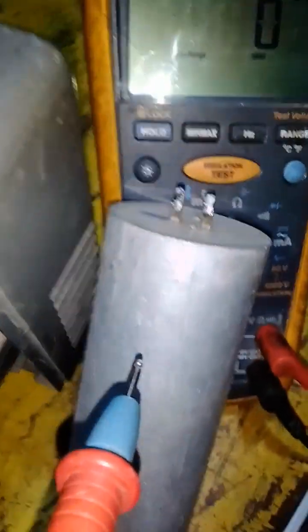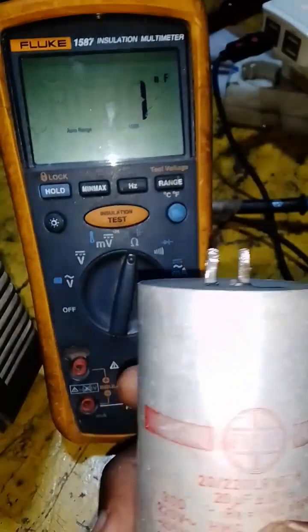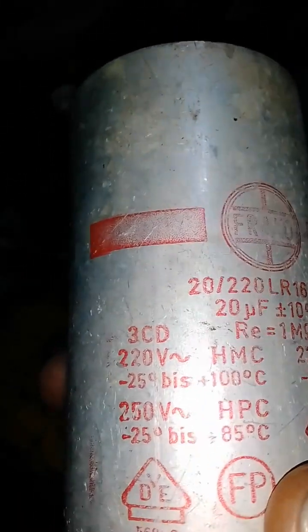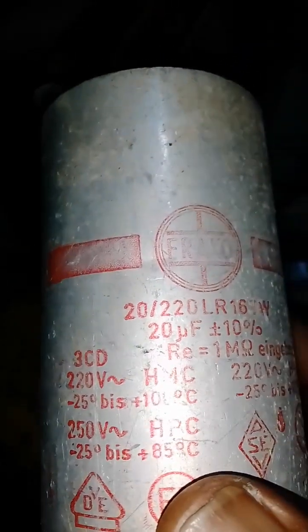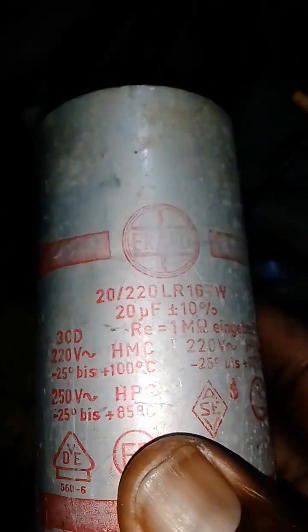It's supposed to have 20 UF, as appeared on this capacitor, as shown here, 20 UF, okay. Let's see the picture very well. Here it's showing 20 UF, 220 volts AC and 20 UF. So that's what it's supposed to have here, 20 UF, to show the capacitor is okay. But this is showing 0, which means it's bad. The capacitor is bad, okay.